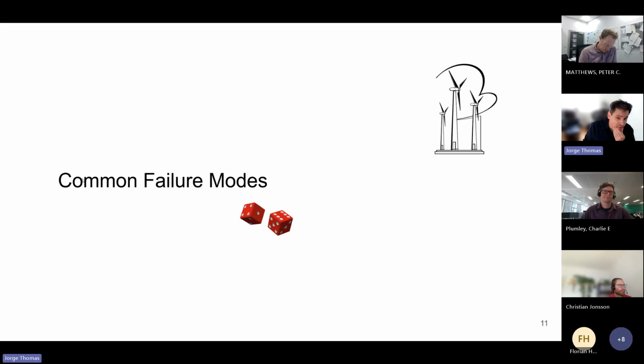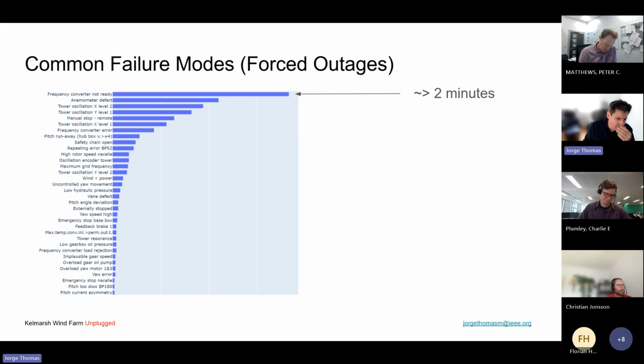Now common failure modes, a quick review of just the forced outage events. We have 'frequency converter not ready', a really annoying failure, a 2 to 2.5 minute reset, maybe related to synchronization with the grid. It's very frequent but very short, so not that important.